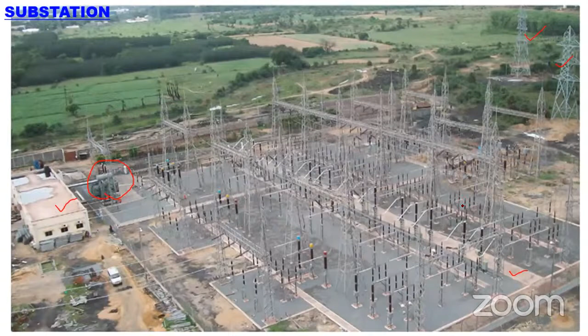Then how the transmission line is connected. So the transmission line is connected with the steel structure through insulator with the conductor. Then the conductor travels all along all the equipment which I told you: disconnector, lightning arrestor, disconnector, voltage transformer, then circuit breaker, current transformer. Then it's connected to your bus bar. Then from the bus bar, one more time, the disconnector, circuit breaker, CT, VT, then lightning arrestor, and it will connect to your transformer. So this is what we need to understand about the layout.